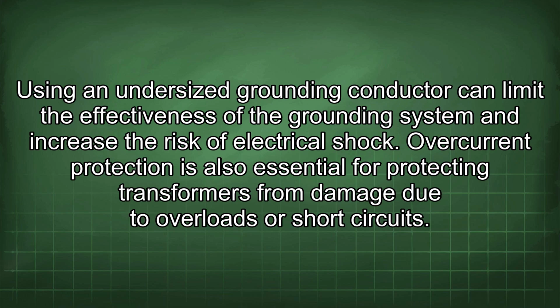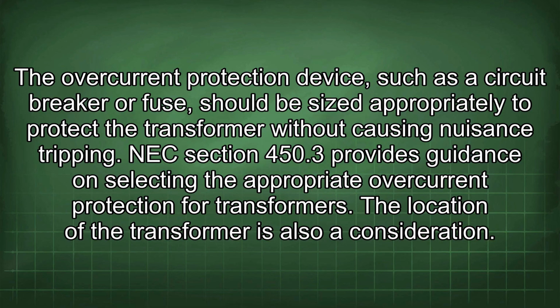Overcurrent protection is also essential for protecting transformers from damage due to overloads or short circuits. The overcurrent protection device, such as a circuit breaker or fuse, should be sized appropriately to protect the transformer without causing nuisance tripping. NEC Section 450.3 provides guidance on selecting the appropriate overcurrent protection for transformers.